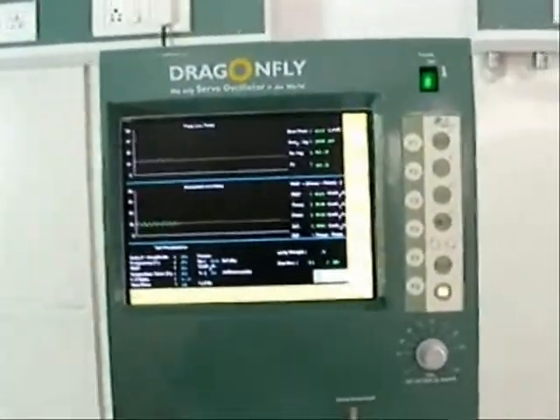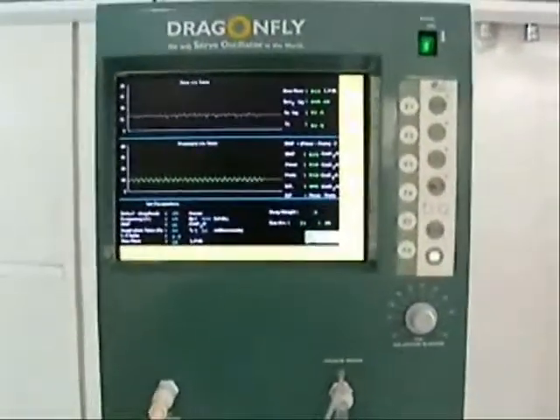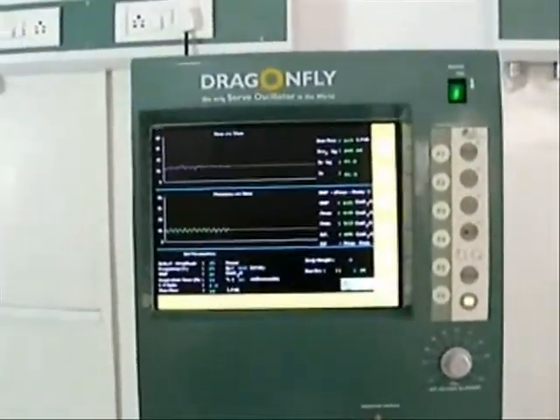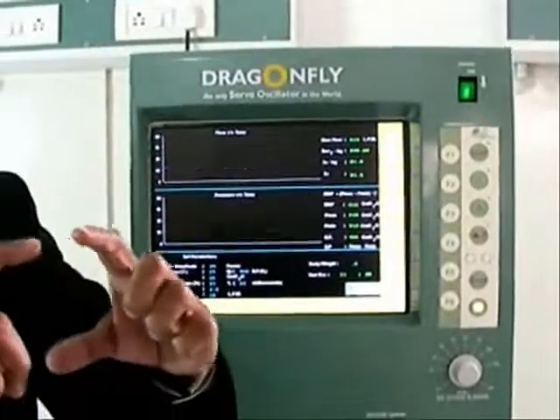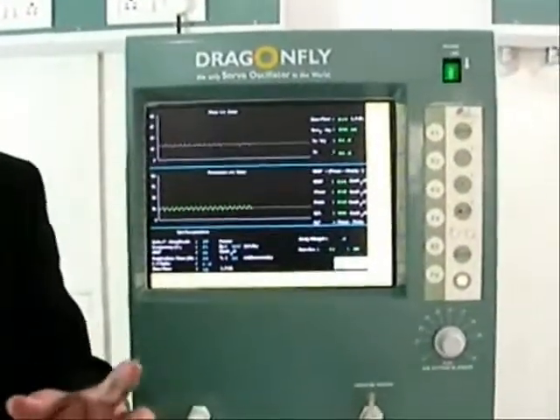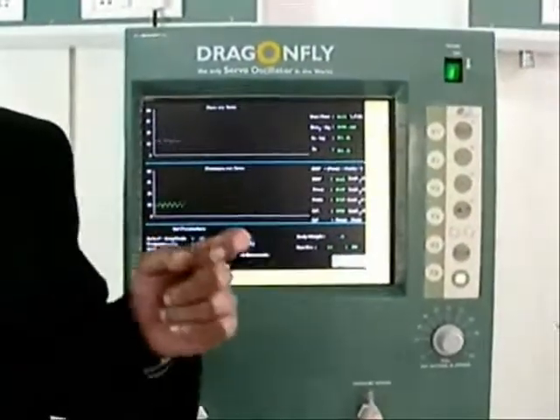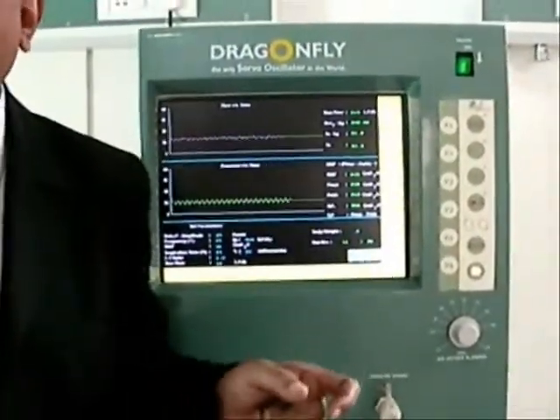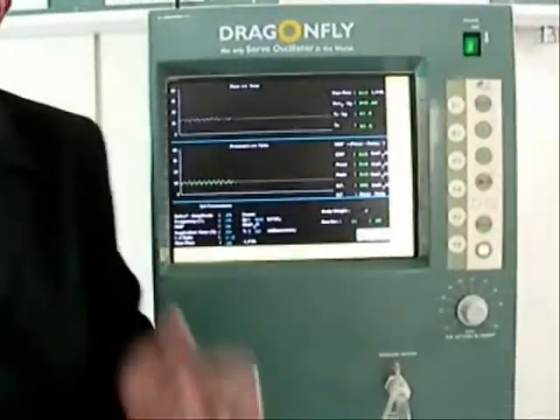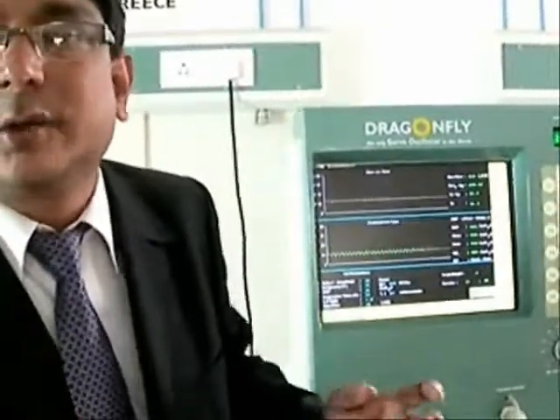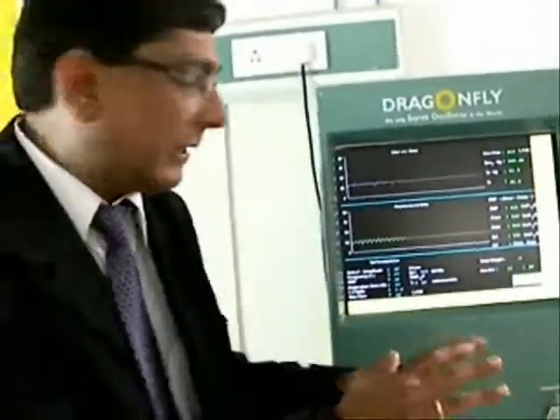And those are the end-user advantages that we have, wherein the piston need not be adjusted. Yeah, that's a good question. Actually, the most popular high frequency ventilator until a few years back was the SensorMedics 3100A. But in that, you have to adjust the center positioning of the magnet in various cases. Here, once you put up the machine, the piston automatically goes to its resting position, that's at zero. So you need not adjust the piston positioning, and that's a very big advantage, because on the SensorMedics, if I don't adjust the piston positioning, my volume or my amplitude changes, and that's quite risky.